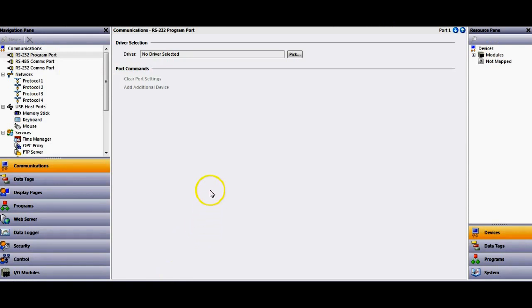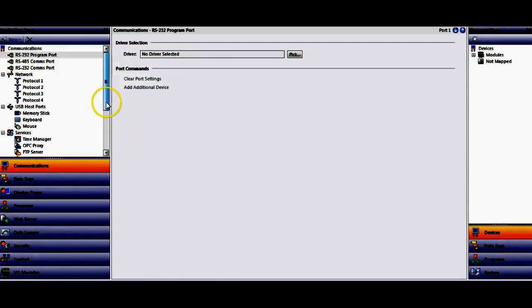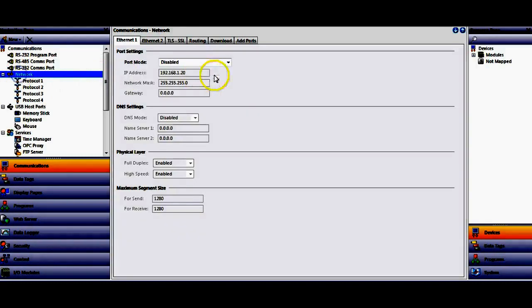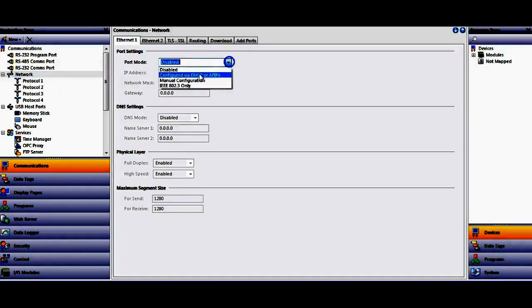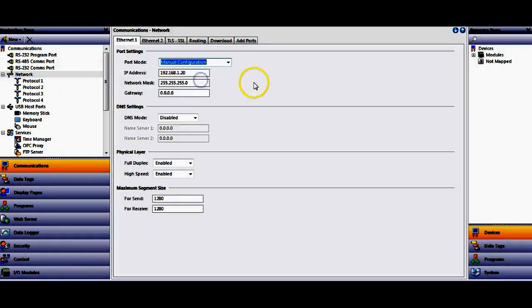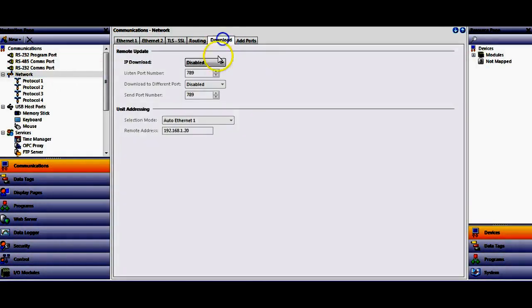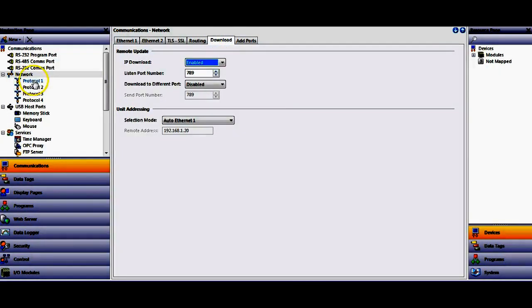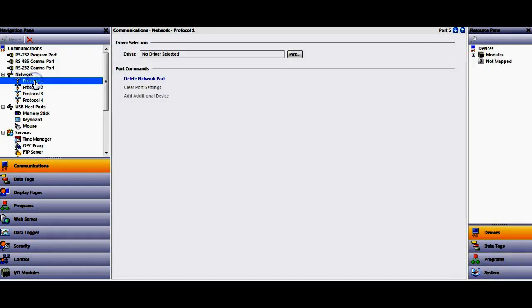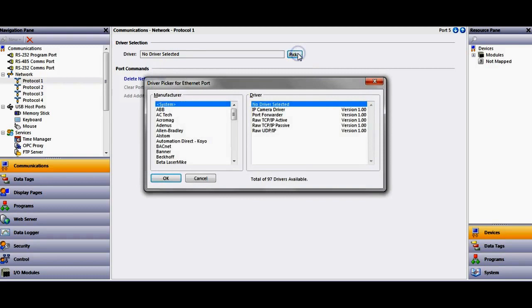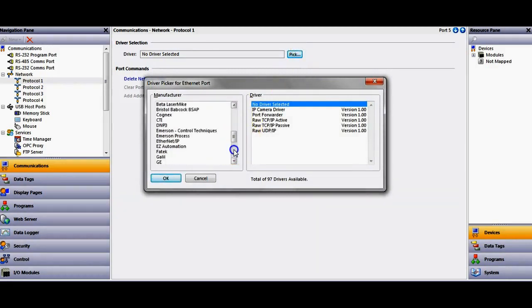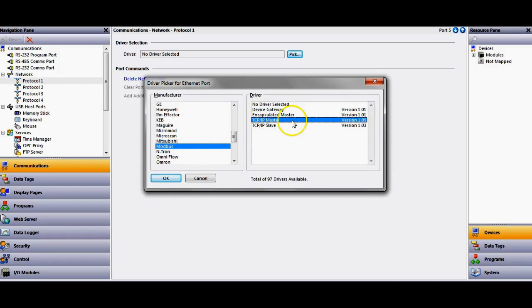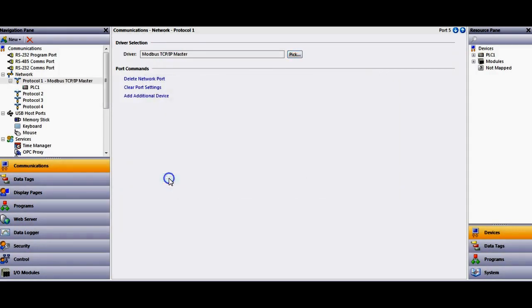So I'm going to go open up Crimson 3. I've got an HMI here. I'm going to go ahead and set up my Ethernet port, choose that. I'm going to download over Ethernet. This is how I like to do it. If I click on Protocol 1, I'm going to choose the Modbus driver here. So we'll go down here to Modbus right here. We're going to set up the HMI to be a TCP IP master. Click OK.